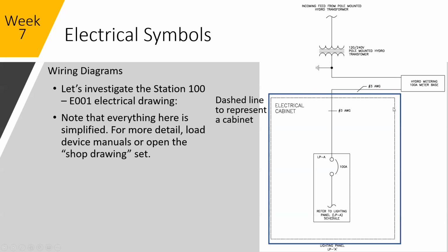This dashed line here indicates that this is a panel of some sort. This note here indicates it's an electrical cabinet. The power comes down, you can see it goes into LPA, which comes into a 100 amp breaker. We know that's a breaker from one of my previous slides. There's its rating. It comes down to this little squiggly. I don't know if there's a real term for that, but that indicates that there is a break and we need to go elsewhere to get more information. We need to refer to lighting panel LPA schedule.